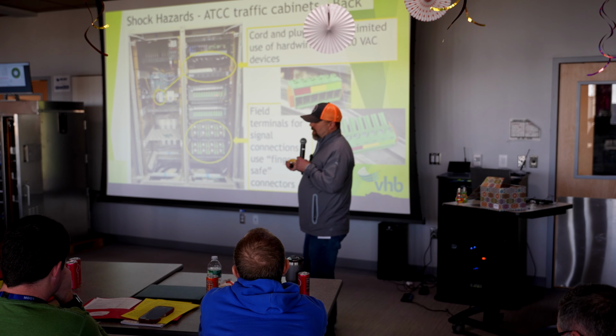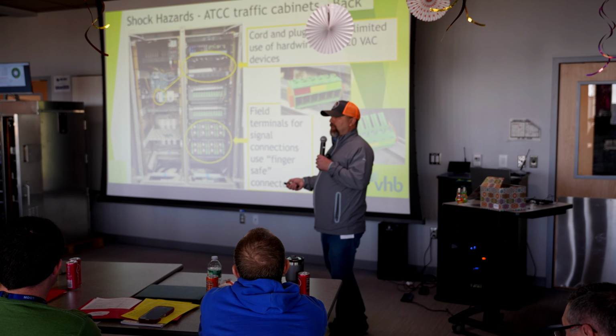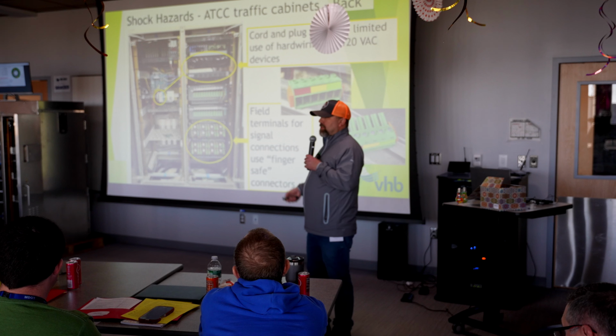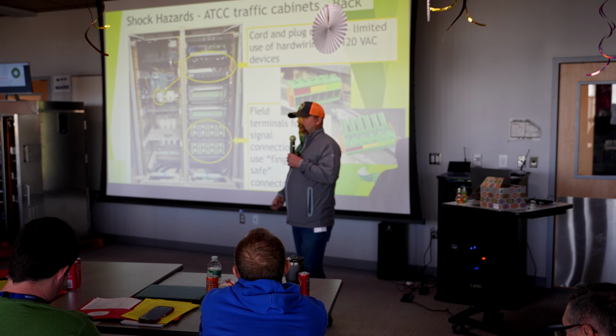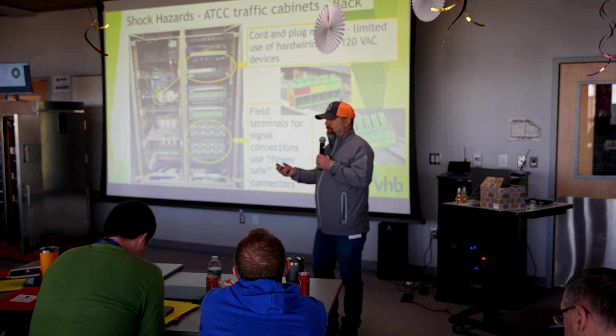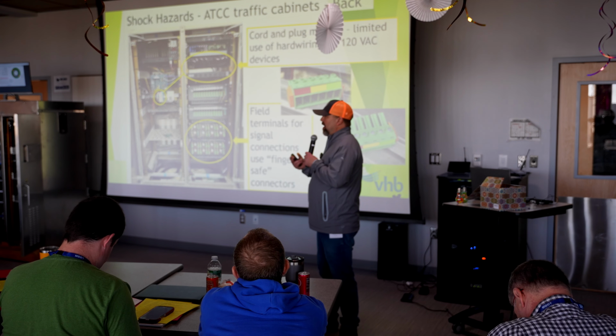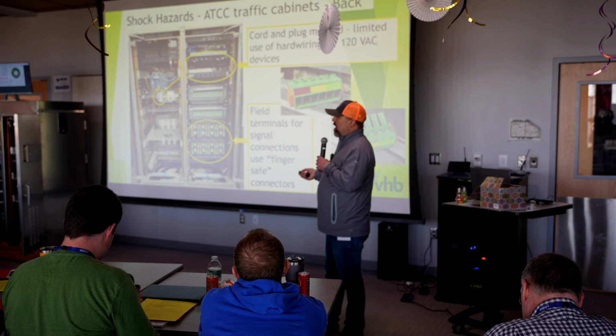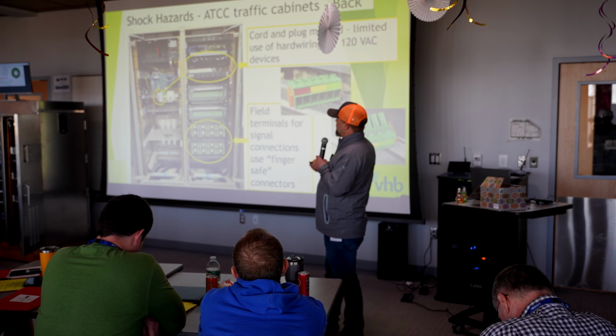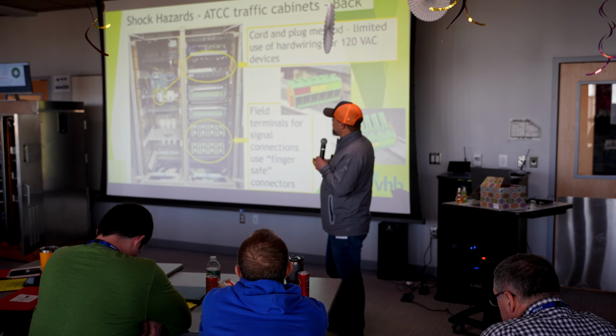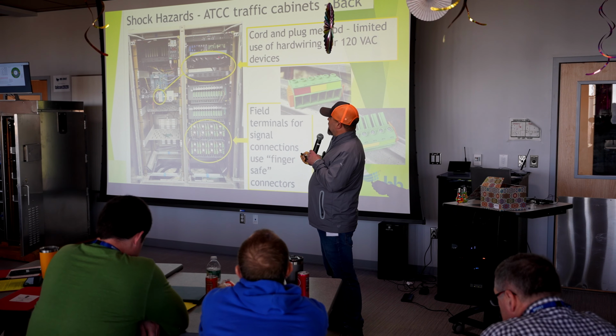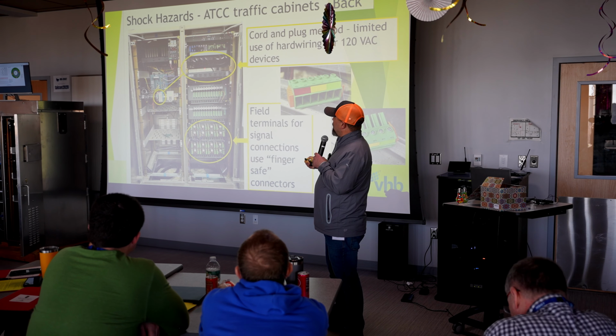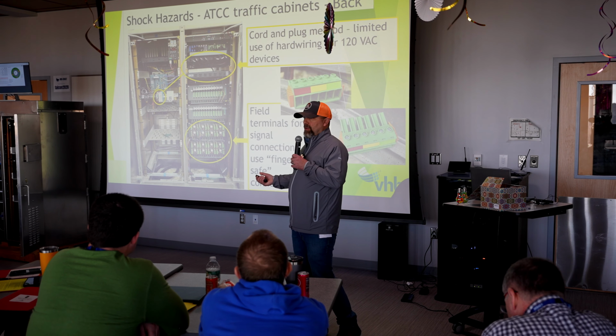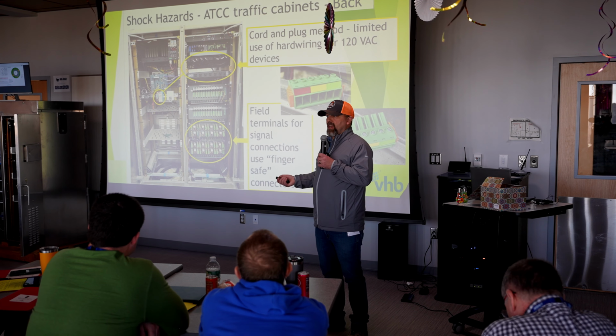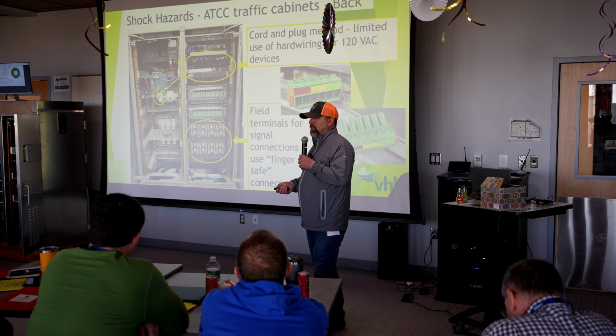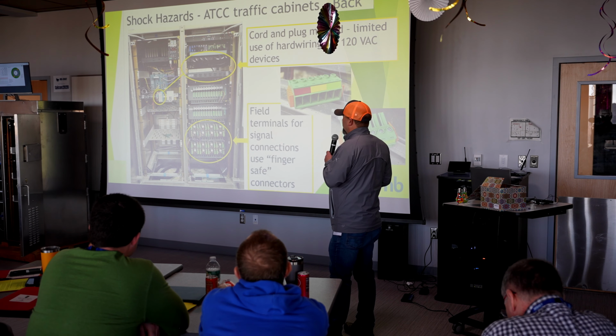One major improvement with this platform is that everything pretty much becomes plug and play. You're not really hardwiring anything, not stripping out wires, putting fork terminals on them, and landing them on a terminal. By and large, most devices added to this have a cord and plug. You'll notice this top one is almost fully populated, but most cabinets give you an auxiliary set, so you shouldn't run out of receptacles to plug devices into anytime soon.